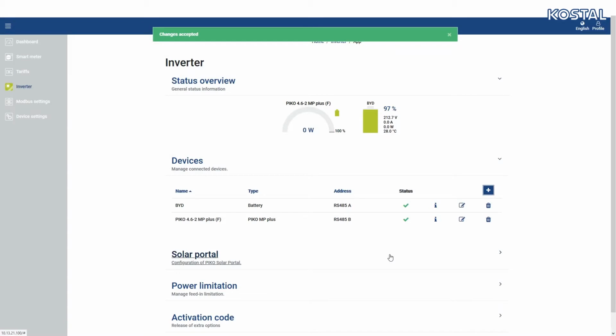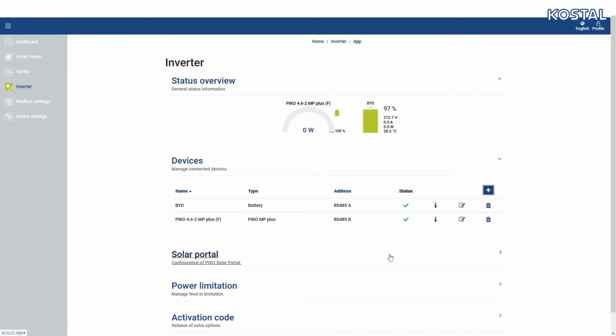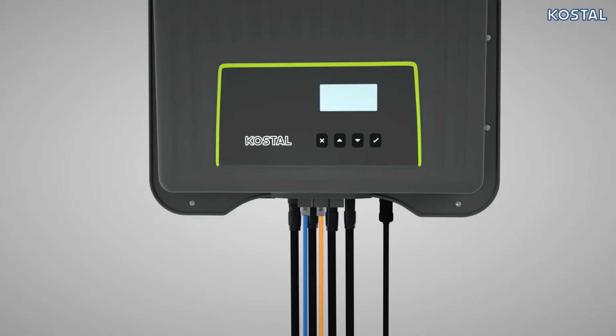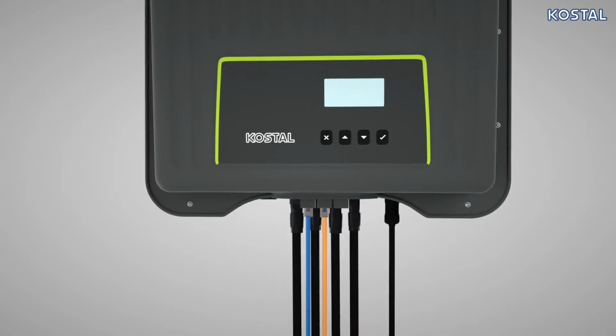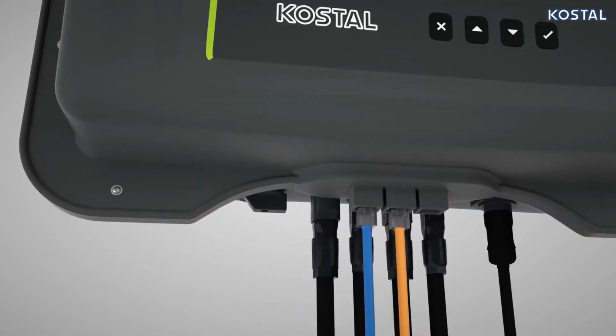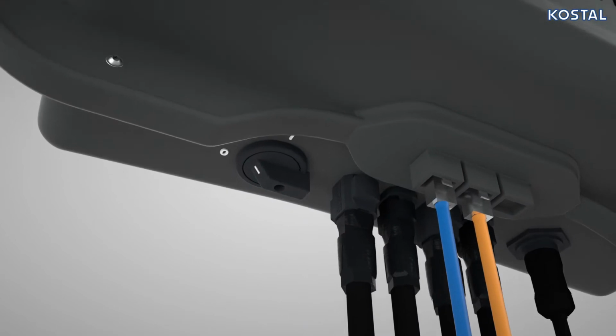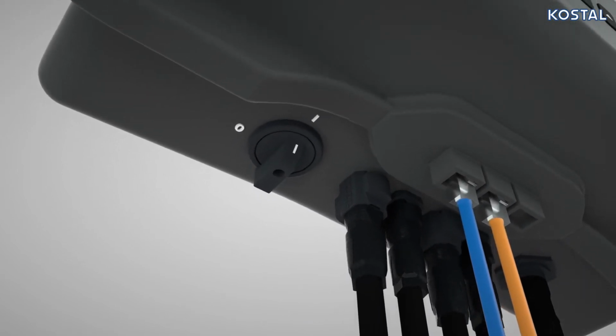Under Status Overview, you can now see all the battery's values, including the charging status. Your inverter and battery are shown in the Devices menu. Finish by moving the DC circuit switch of your PIKO MP Plus to the on position. The inverter now launches on the grid, and you can use the battery.